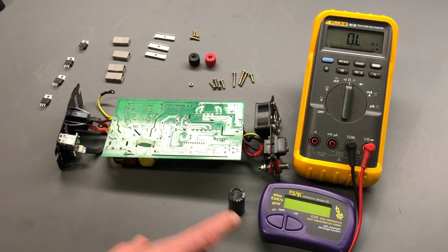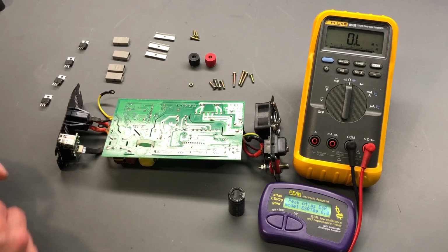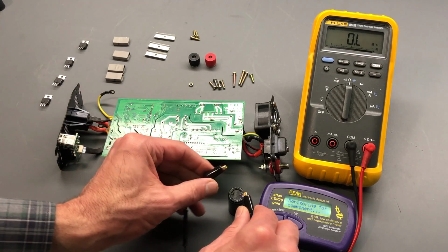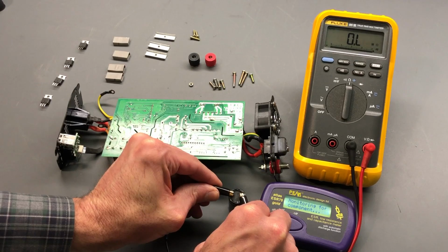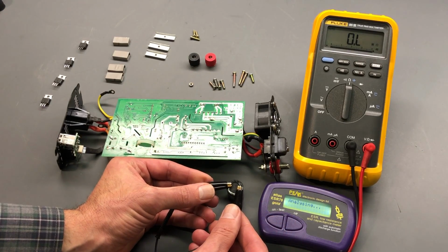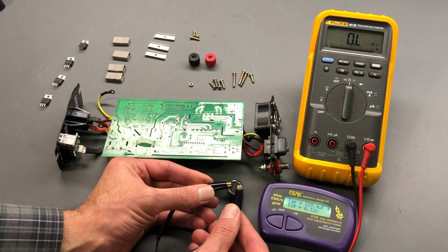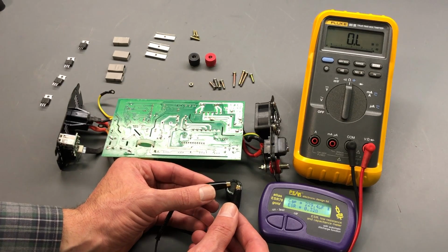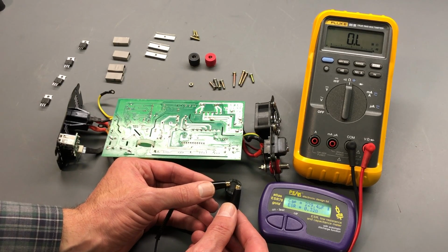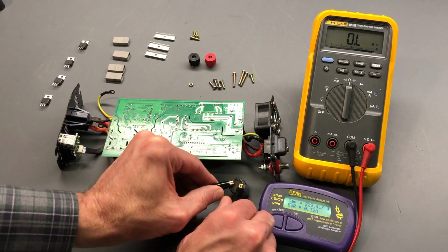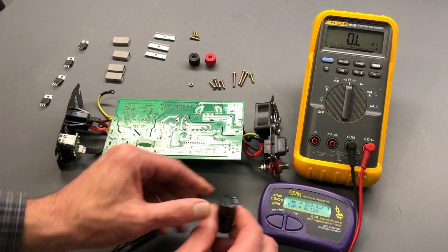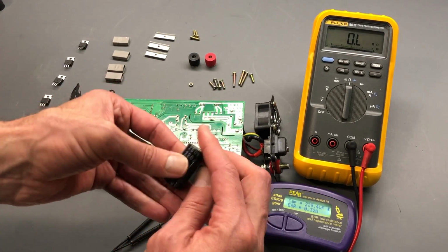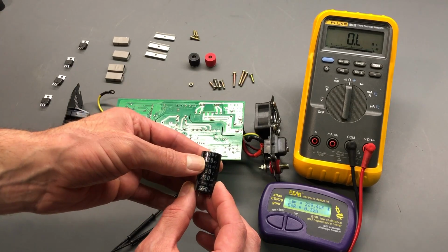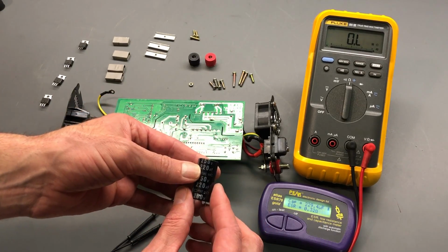But let's take a look at this capacitor. So if we run a quick test on it, an ESR of 0.32 ohms, so not too bad. 229.4, almost 230 microfarad. So the actual rating on this capacitor is 220 microfarad, so we're right there within spec.